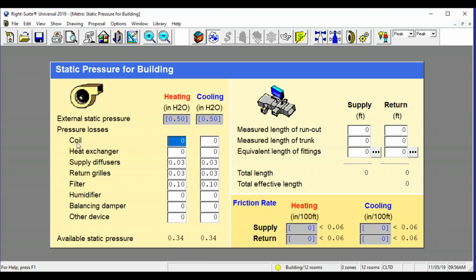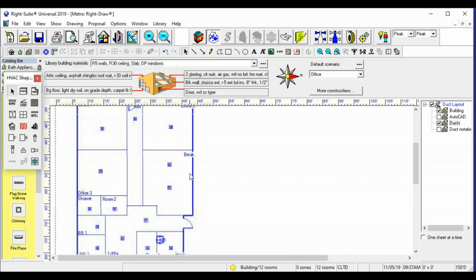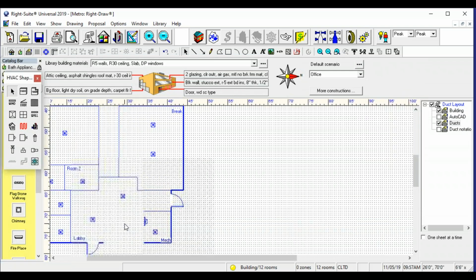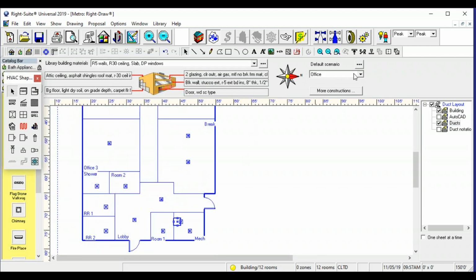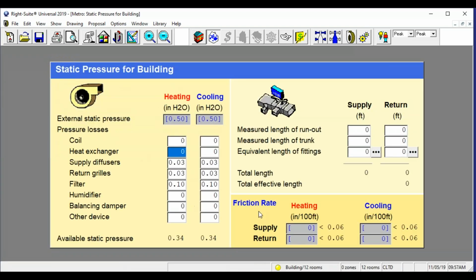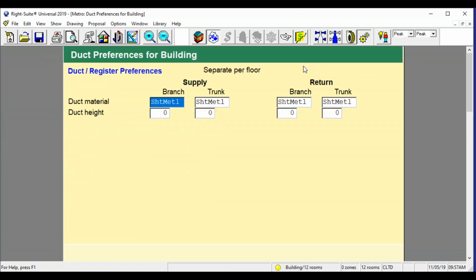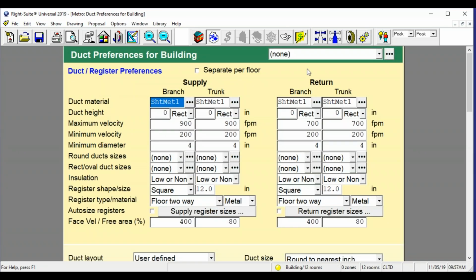Your blower fan heat is actually incorporated in the capacity of the unit when the capacity was being established for the unit. You'll see a lot of people will add more BTUs for that blower fan, and it's completely not necessary. You're being redundant at that point. And the more redundant you're being with adding extra stuff into it, the less accurate you're being on your load. All right, so we have that done. We went ahead and we set our static pressure. We have that complete. Let's go to our duct preferences.